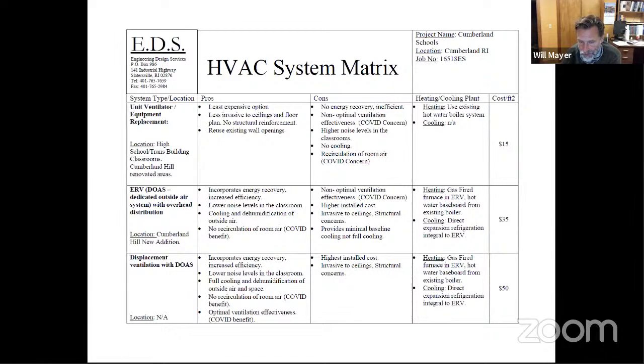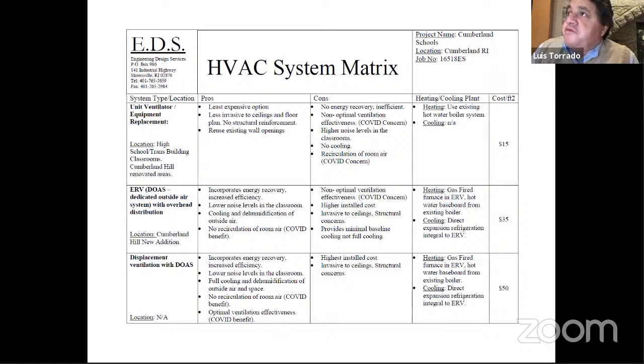So the ERV is a decoupled system. Basically, heating is provided in a completely silent fashion by the baseboard heat, and the ventilation comes in through the energy recovery unit. When we typically provide these systems, we tell school departments it's going to feel like a little bit of air conditioning, because it gets rid of the humidity.